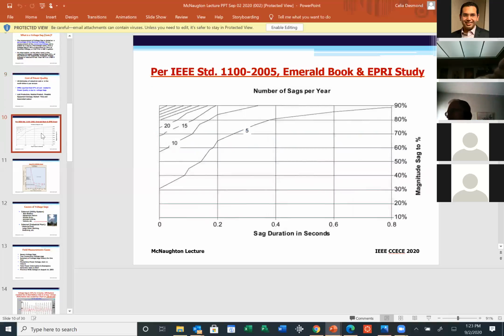This is a chart that was produced by the IEEE Standard and by EPRI. I want you to look at the area from 0 to 0.2, where 0.2 is seconds. In other words, look at the duration. Most of these recorded events fall into this area, 0 to 200 milliseconds. As far as the voltage drop, the shorter the duration, the more severe, because one would expect these events to take place mostly on what we call high tension lines. The protective equipment there operates very fast, typically in about 3 to 4 cycles, which is 60 to about 80 milliseconds.